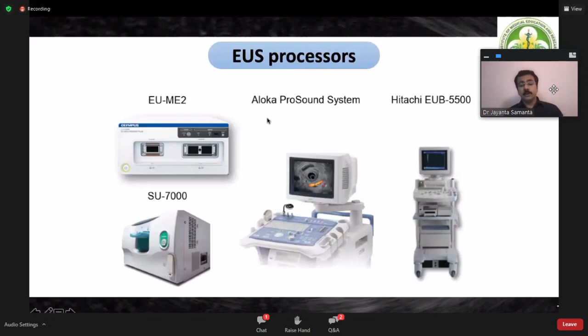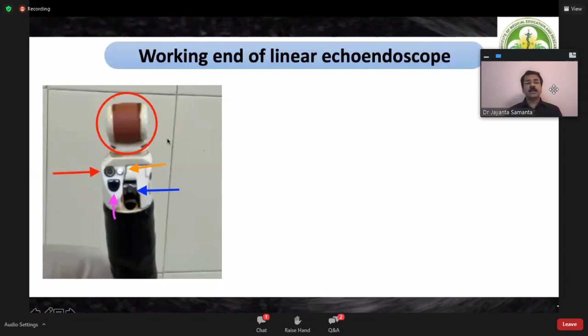So I'll now go into slight details of how the working end of a linear echoendoscope works. This is the ultrasound probe that is there at the tip. This is the camera that we can see over here. The disposition of the camera as well as the working channel and the elevator is exactly like a side-viewing duodenoscope. You can imagine that this is basically a part of a side-viewing duodenoscope above which a transducer has been attached. If you see a lateral view, you will find there is a groove over here where we attach the balloon.